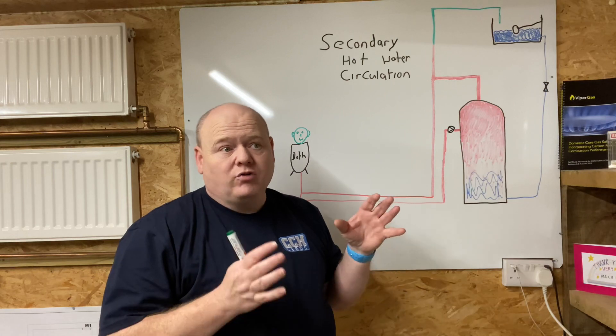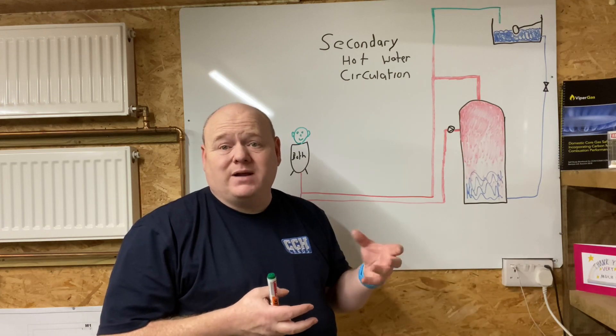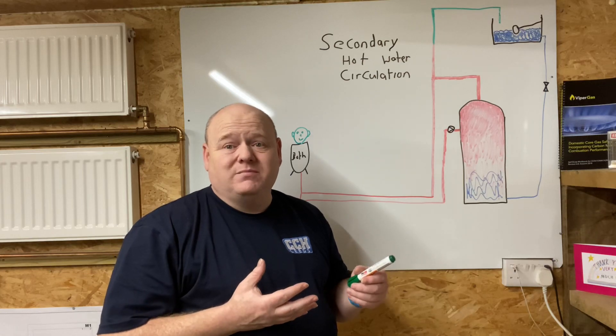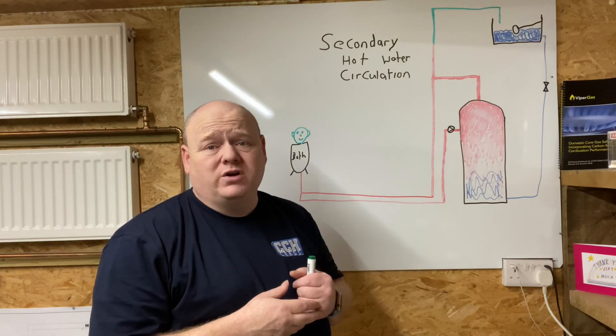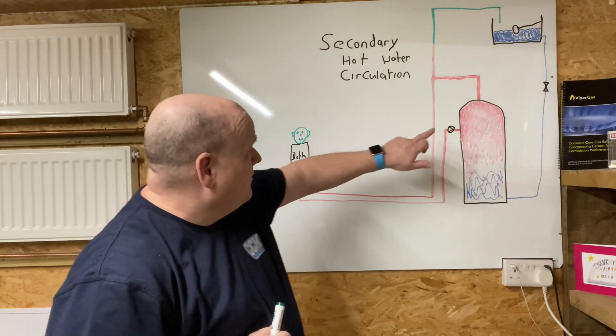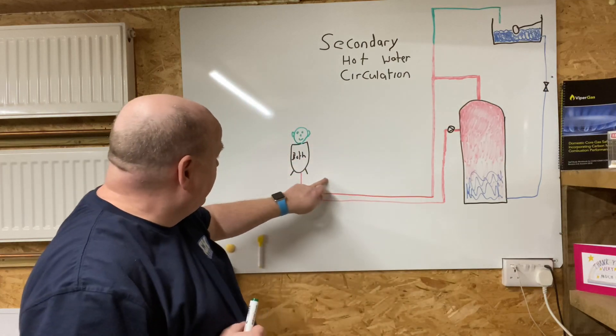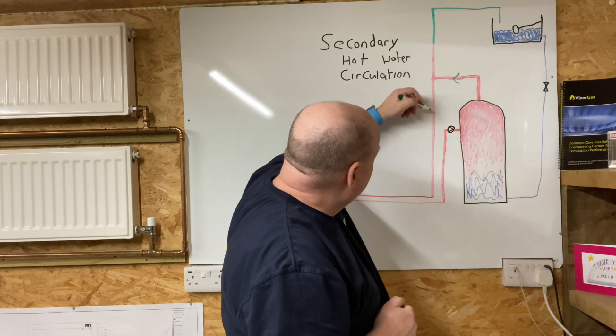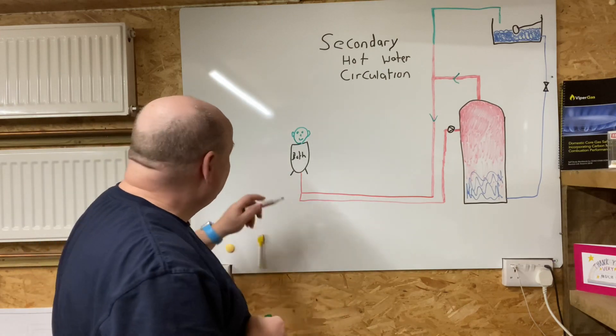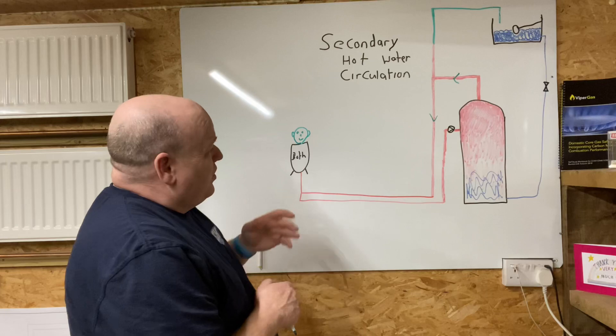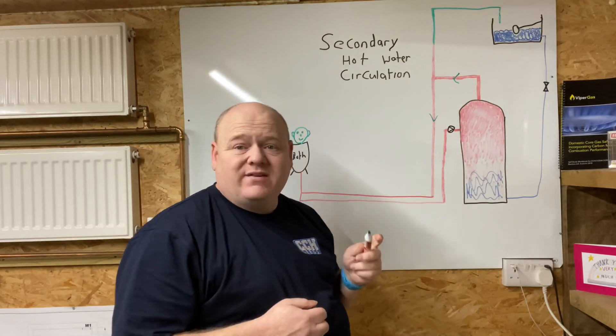On small domestic systems we tend to just put up with the fact that it takes a while, but if you've got a slightly larger system you could put a pumped return on. How a pump return works for your hot water: imagine your normal hot water cylinder with hot water coming off it going off in this direction to a bath. What a secondary return does is make this into a loop, so instead of having dead legs in the system you create a circuit.